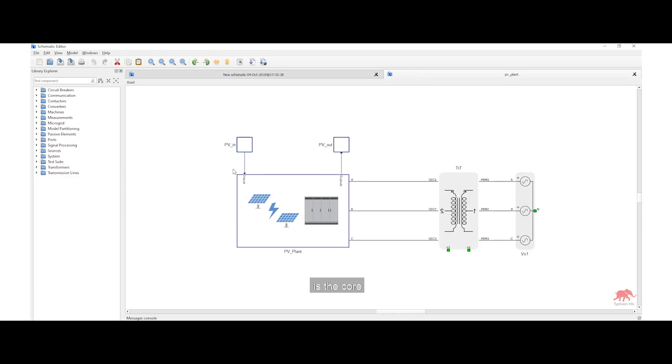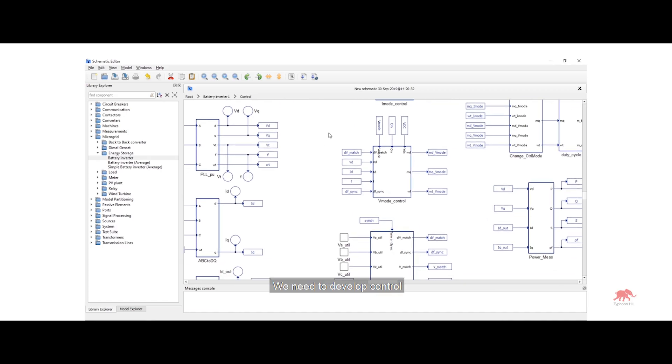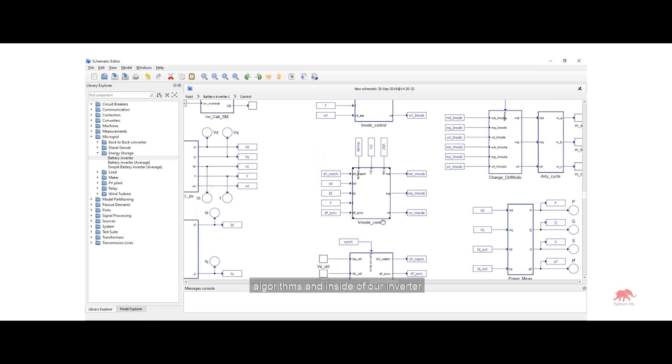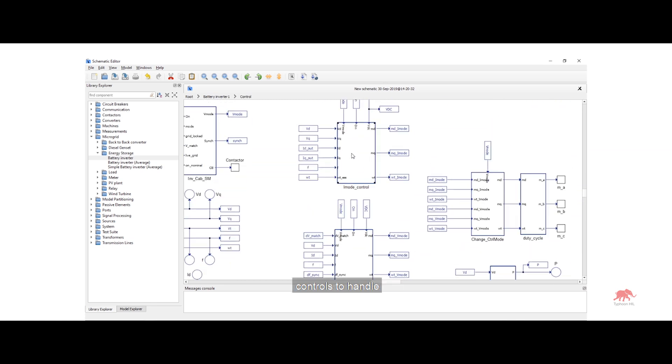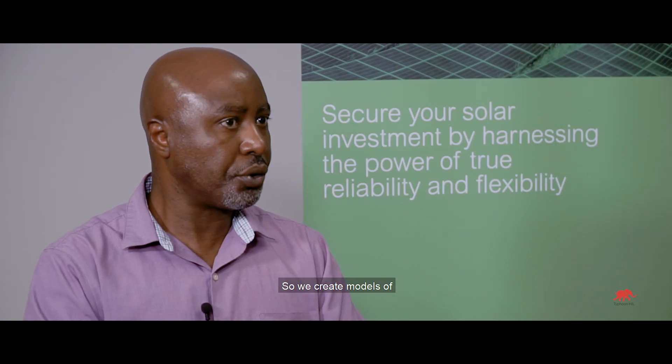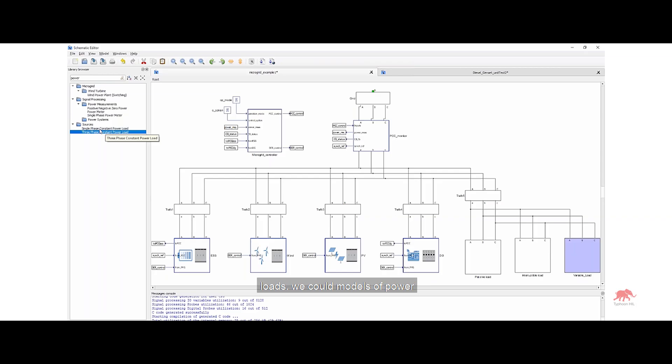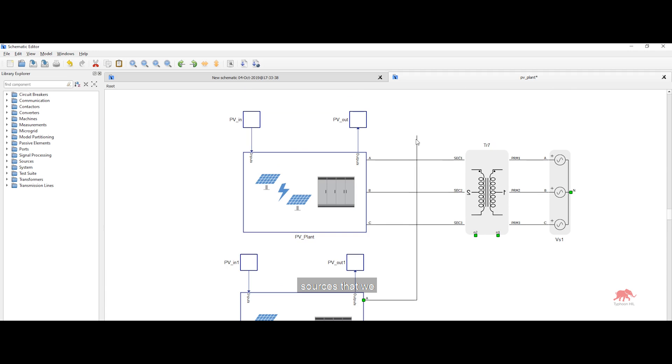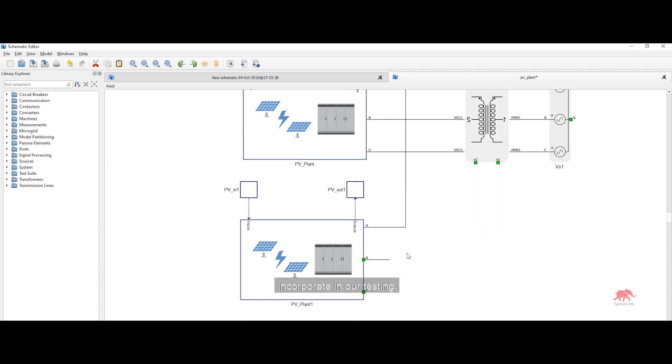The Typhoon HIL is the core of our hardware in the loop platform. We need to develop control algorithms inside of our inverter controls to handle these different grid disturbances. So we create models of loads, we create models of power sources that we incorporate in our testing.